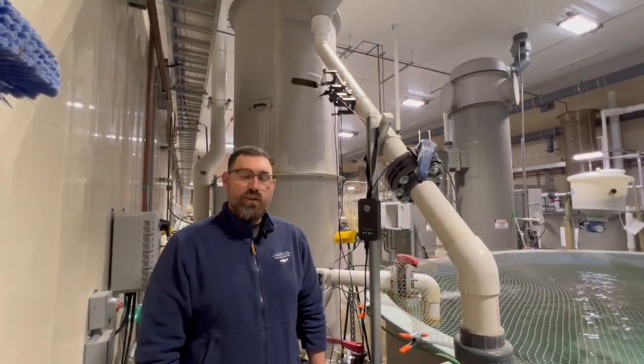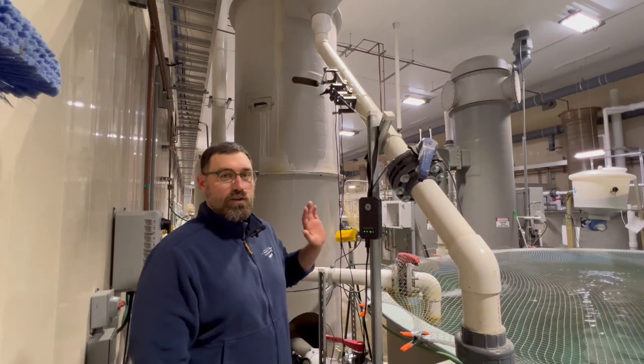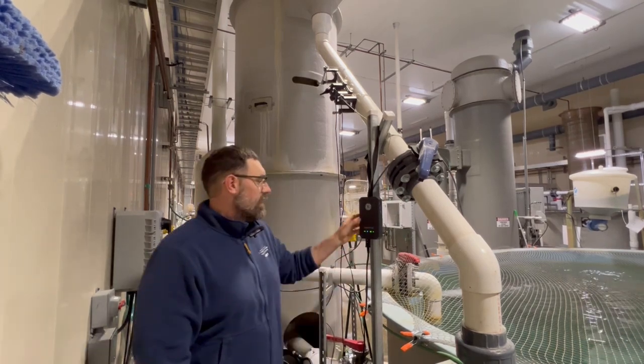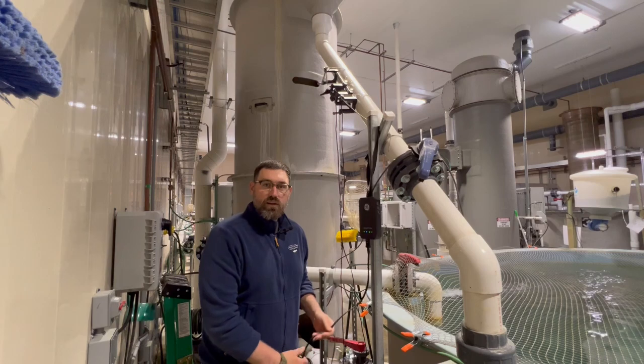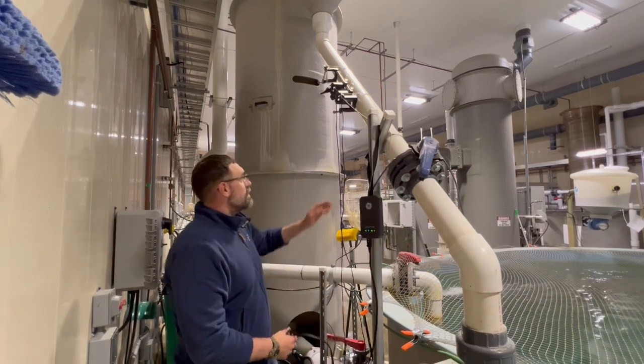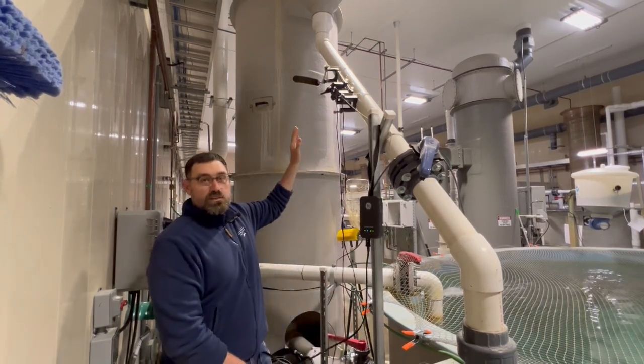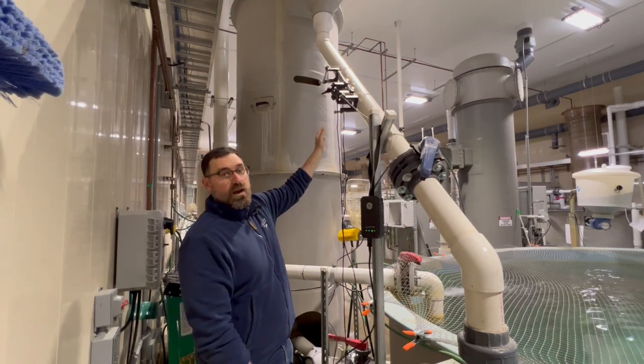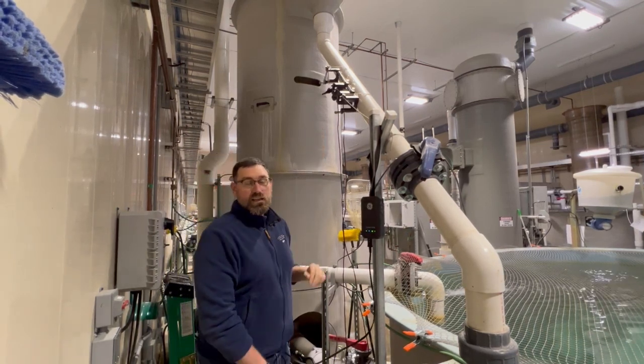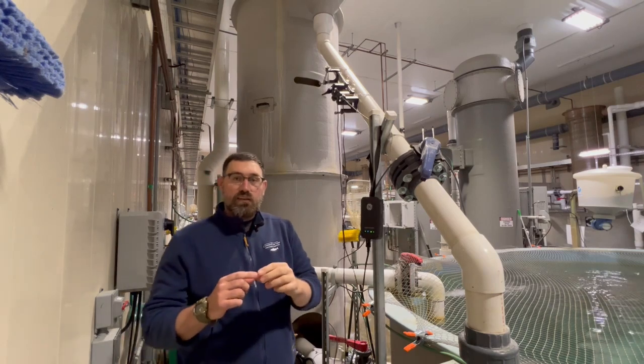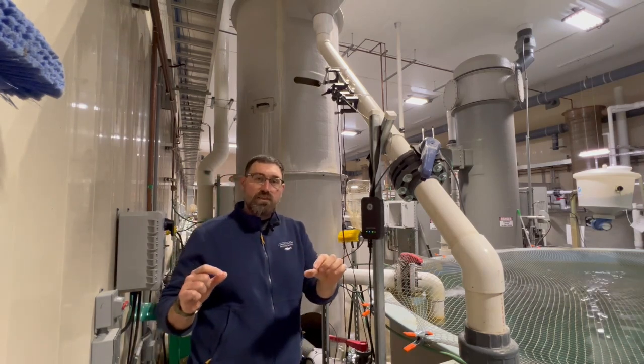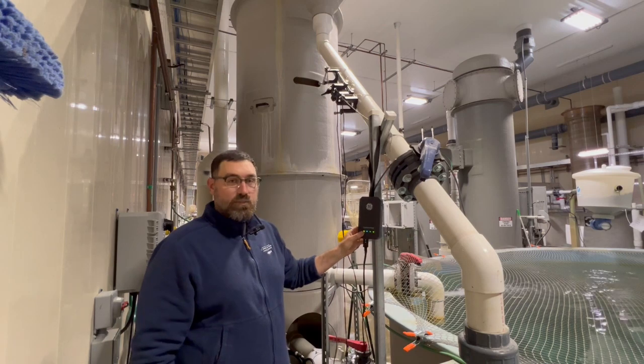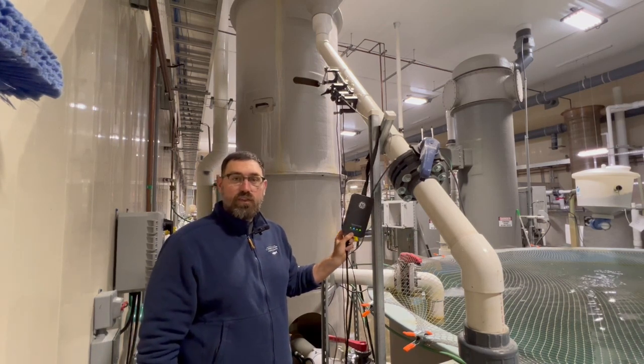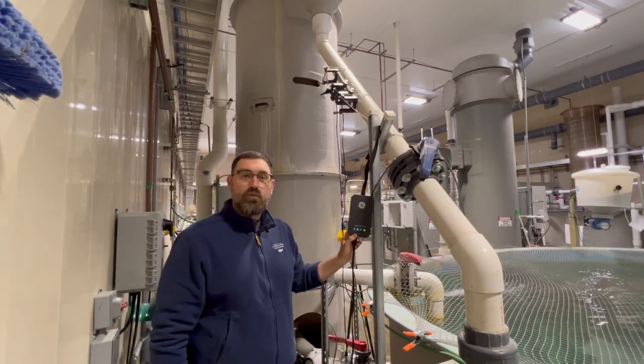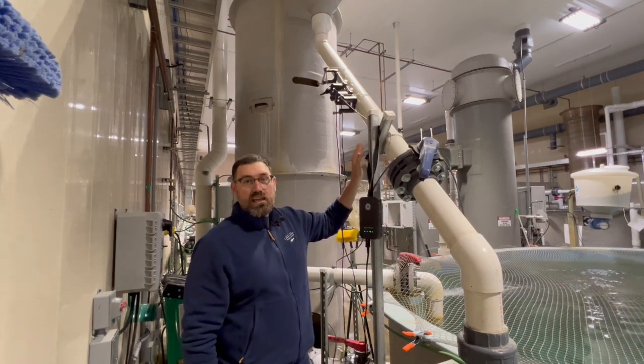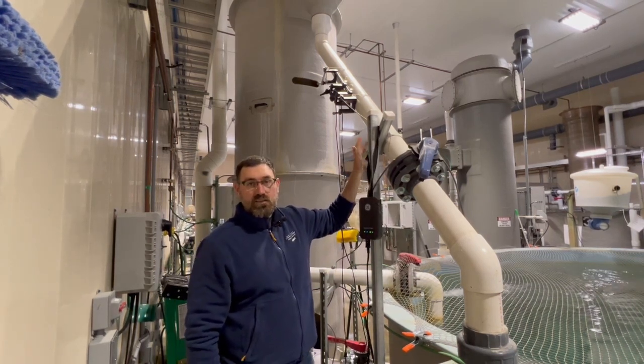So we've installed our ultrasonic flow meter onto our 4-inch PVC pipe. We have the brain of the flow meter attached to the communication cable, which goes up and plugs into the transducers, which are attached to this bracket on the pipe. The transducers are set at a specific length apart from each other, which is set by the manufacturer of the flow meter for getting the most accurate reading you can on a 4-inch piece of PVC pipe.